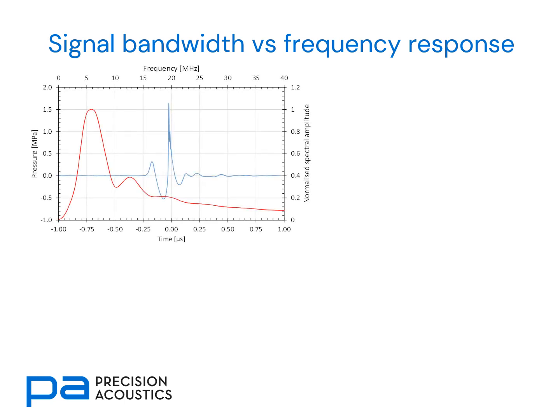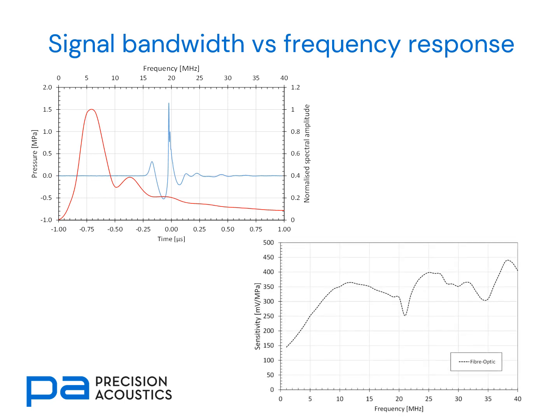Whilst we're talking about frequency response, it's important to consider how that should be compared with the bandwidth of the signals we're looking to measure. Consider the graph here, which shows in blue the time signature and in red the spectral representation of a typical diagnostic ultrasound waveform. Were we to measure that with an optical fibre hydrophone, you can see there is substantial variation over the 40 MHz bandwidth. This is a very broadband source, and measuring it with a response that has substantial variation may introduce quite a lot of distortion in the shape of the waveform. We could correct for this with a deconvolution operation, but it's one more thing to correct for.